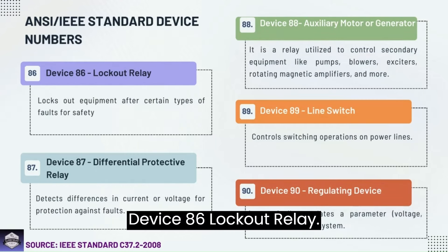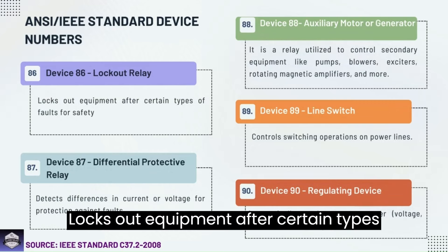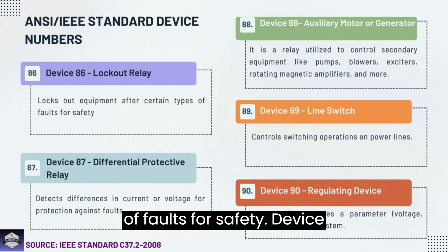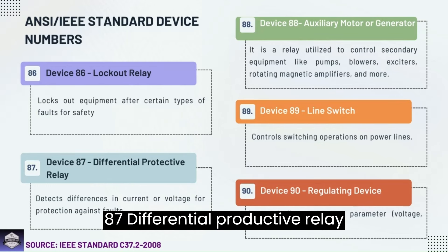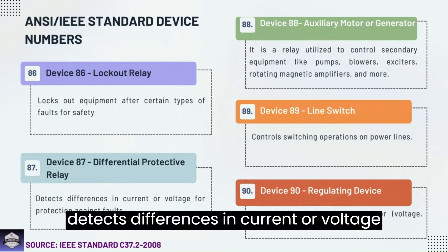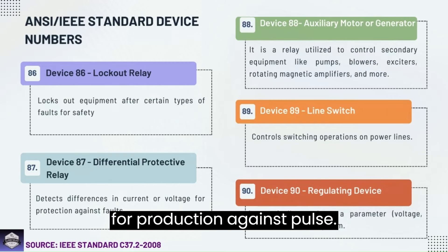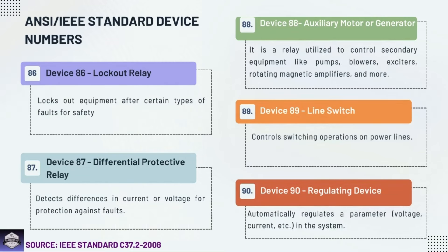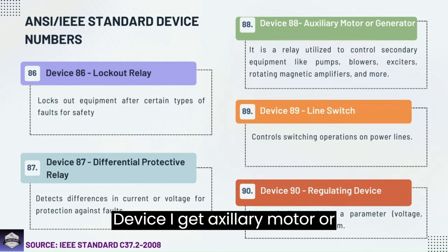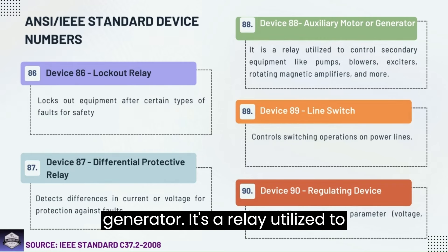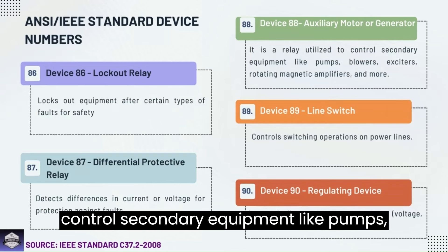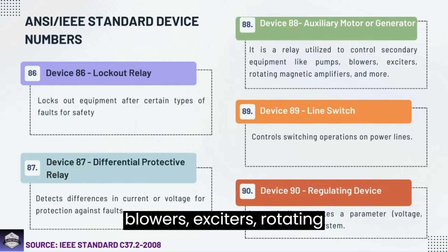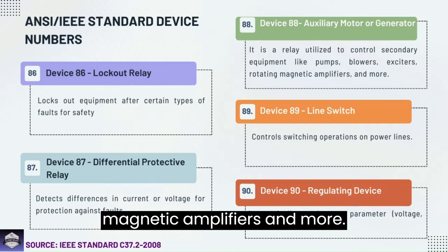Device 86: Lockout relay — locks out equipment after certain types of faults for safety. Device 87: Differential protective relay — detects differences in current or voltage for protection against faults. Device 88: Auxiliary motor or generator — a relay utilized to control secondary equipment like pumps, blowers, exciters, rotating magnetic amplifiers, and more.